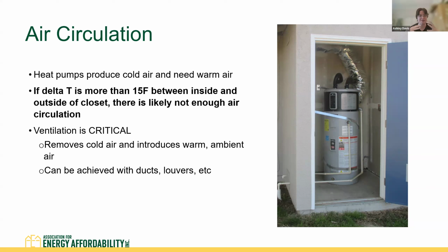You're probably getting a pretty big buildup of cold air inside your enclosure, and your heat pump's not going to run efficiently. It's going to start relying on those electric resistance backup elements if there's too much cold air, because it simply can't pull any more heat out of it. So this means ventilation is really critical. It removes cold air from the enclosure and introduces warm ambient air so that your heat pump can run effectively. This can be achieved with ducts, with louvers. There's a bunch of different ways to do it. Next slide.